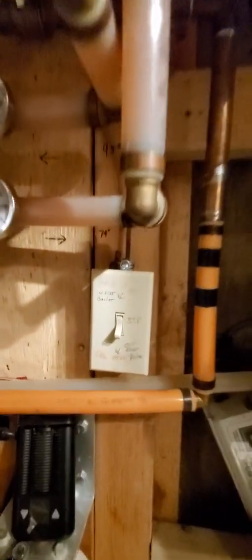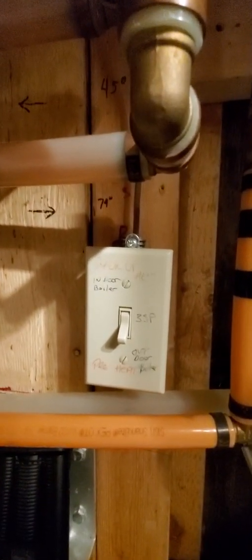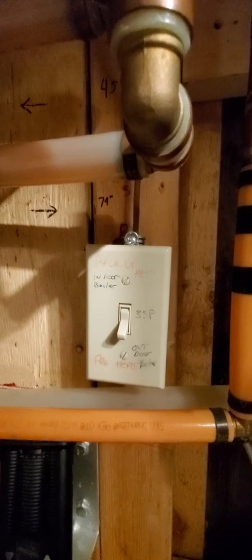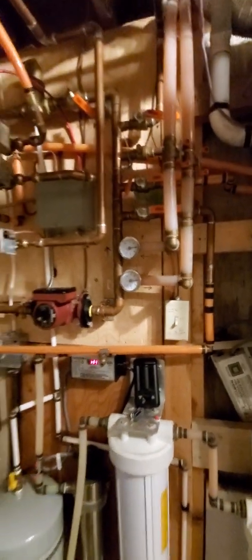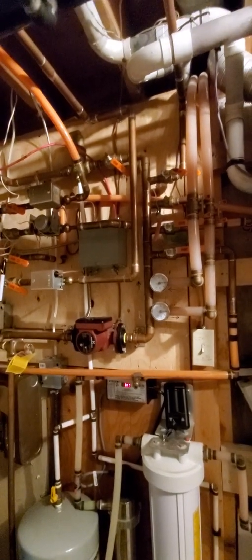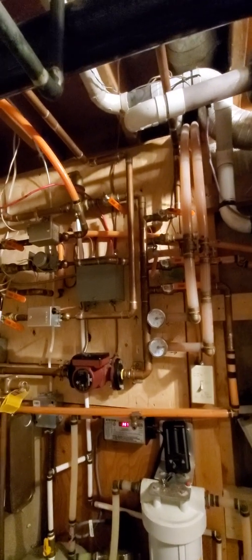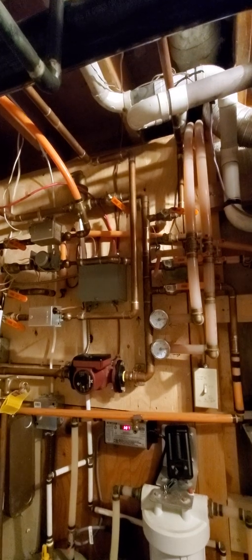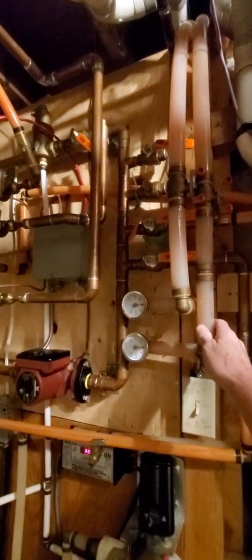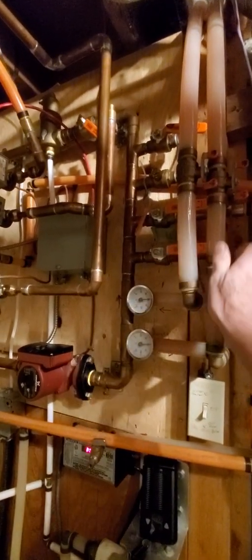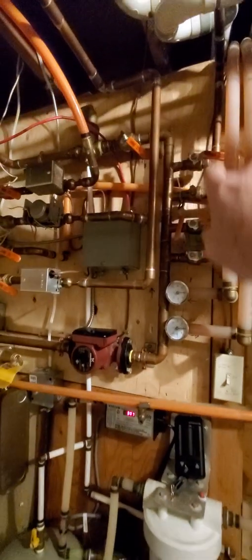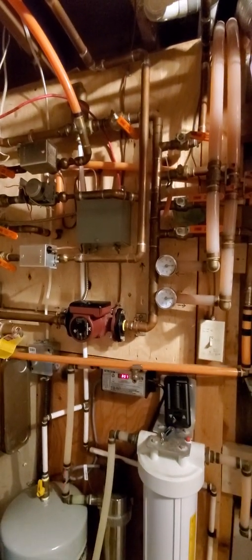And I've also put a switch here, and this is in the down position for winter or outdoor boiler. If I flip it up, that'll just make this a new zone for the natural gas boiler, and that will take over all of the zones in this part of the house as well. And all it does again is cycle hot glycol in and out that follows the loop around. So I'm going to go to my other utility room now.